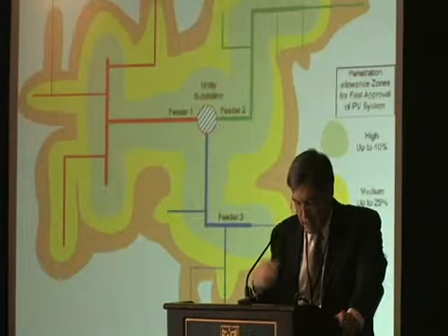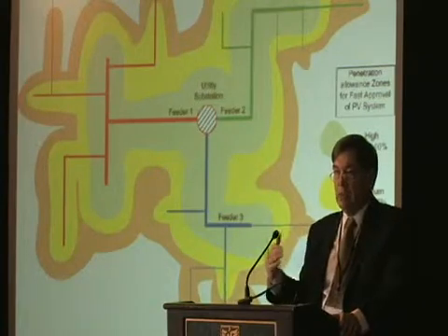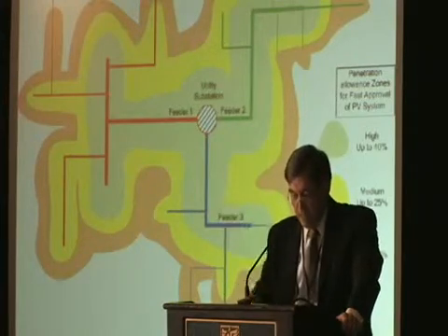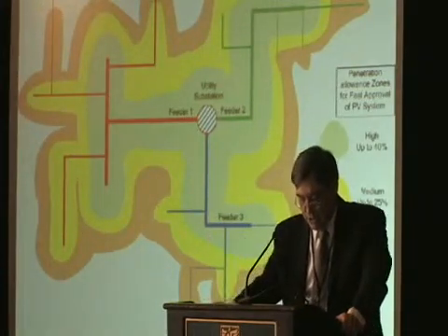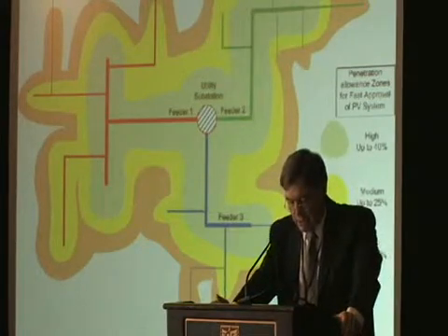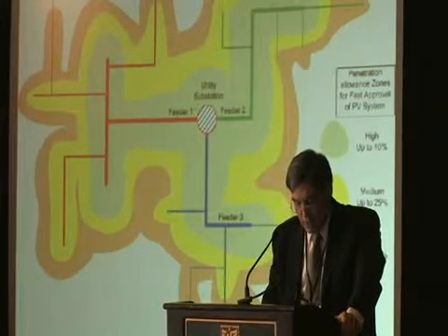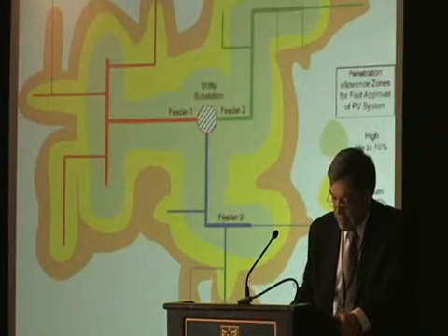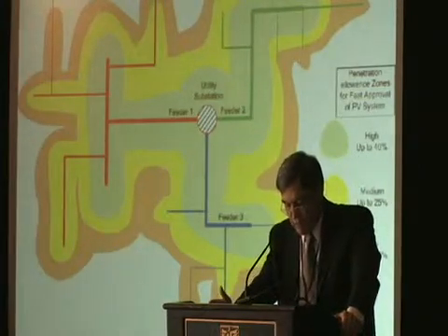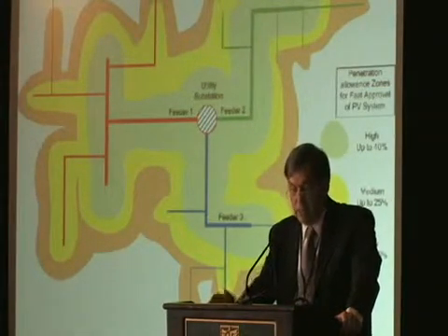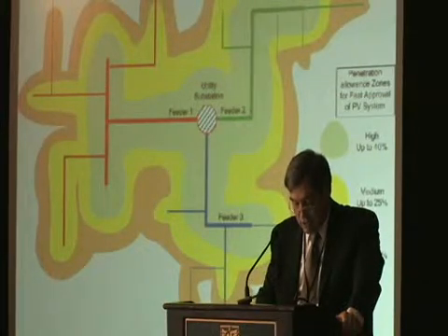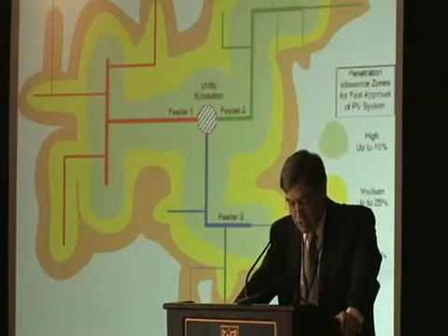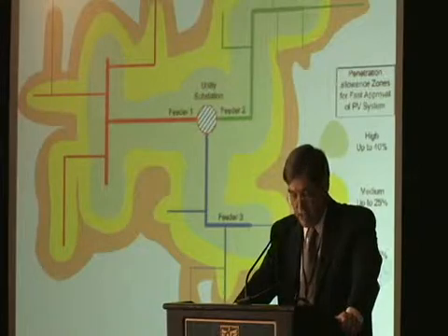And so there's really three approaches that this paper uses to looking at how to analyze a distributed PV in a local distribution system. The first approach is the one I mentioned, which suggests utilizing PV-specific screening criteria that would utilize minimum daytime load for a circuit rather than the absolute minimum load or percentage of peak load. Second approach is applying additional screens to evaluate potential voltage or unintended islanding. And the third one is increased penetration levels in specific areas and zones like this slide shows, based upon substation location, circuit design, and existing DG.